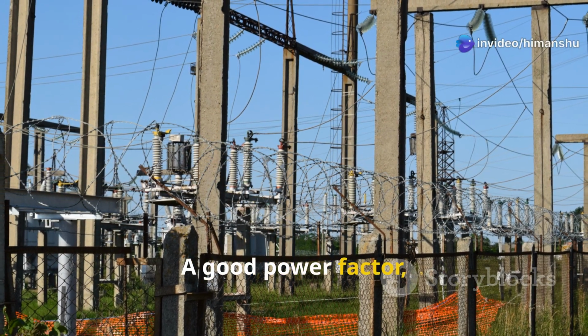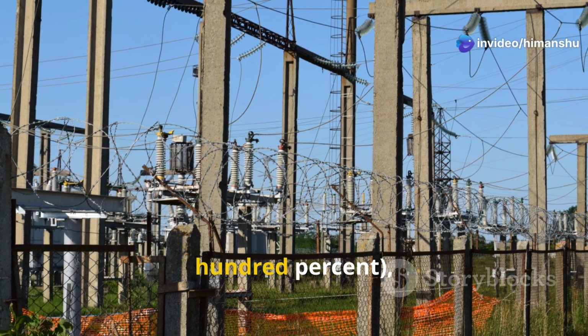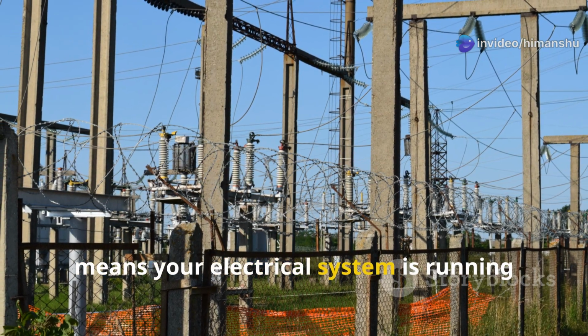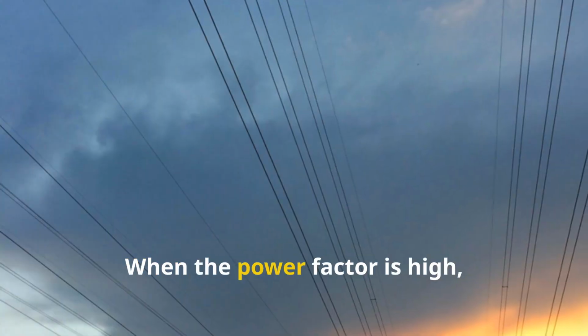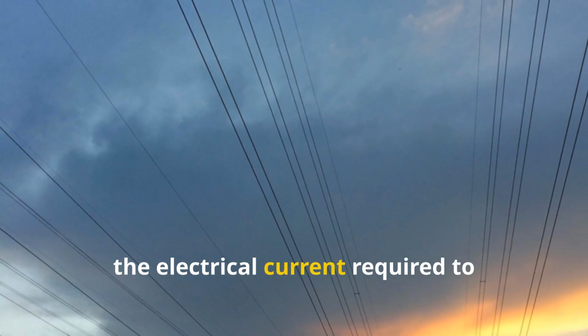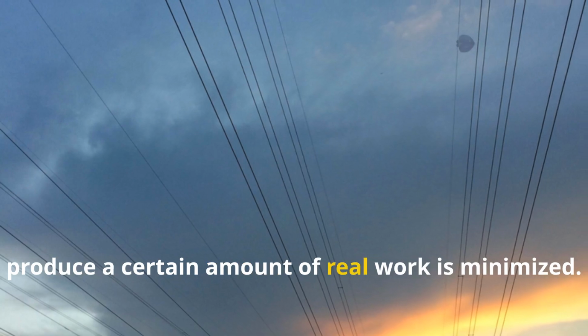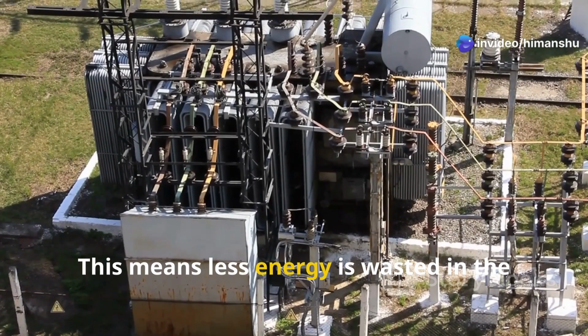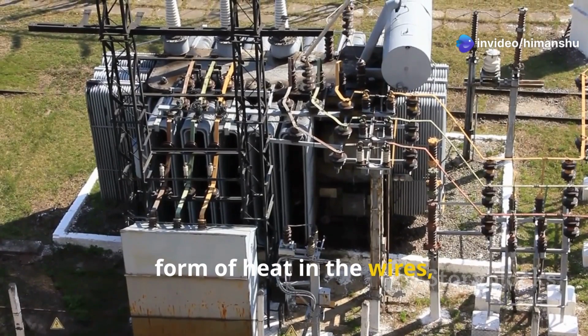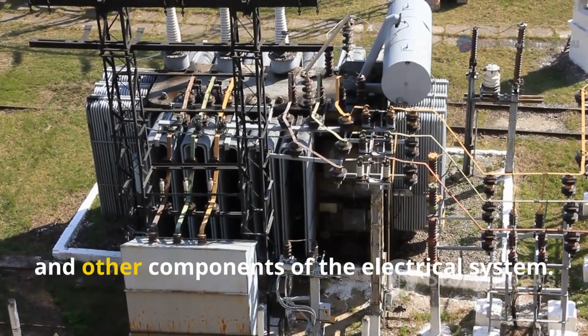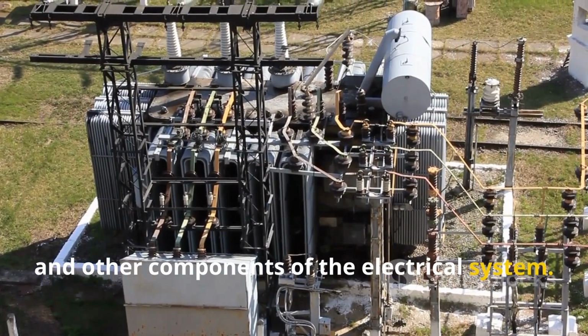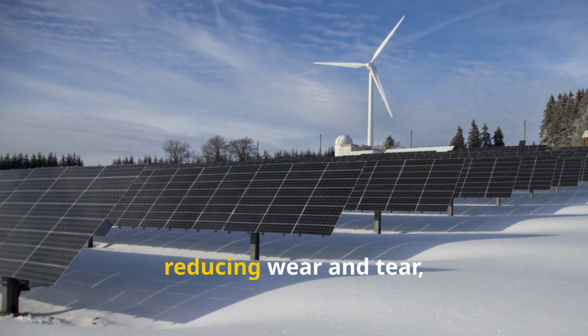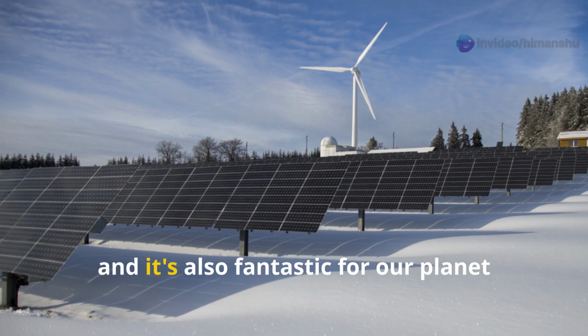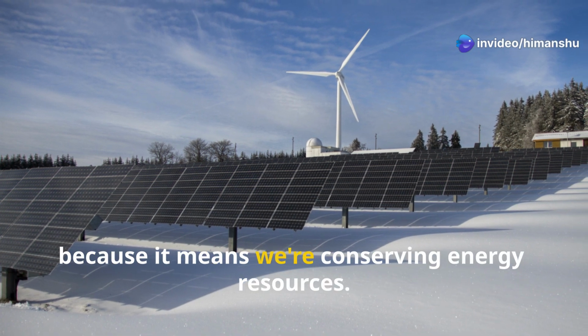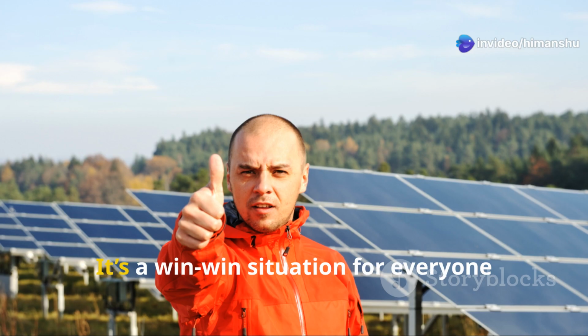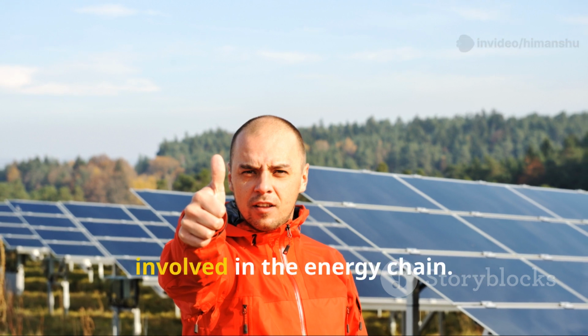A good power factor, one that is close to unity or 100%, means your electrical system is running efficiently and is healthy. When the power factor is high, the electrical current required to produce a certain amount of real work is minimized. This means less energy is wasted as heat in the wires, transformers, and other components of the electrical system. Less waste is good for the equipment, reducing wear and tear, and it's also fantastic for our planet because it means we're conserving energy resources. It's a win-win situation for everyone involved in the energy chain.